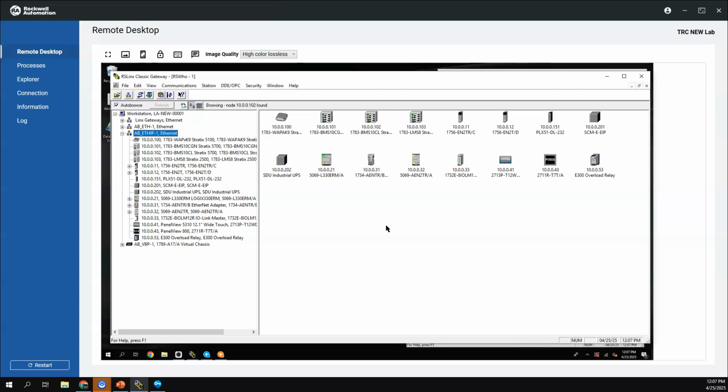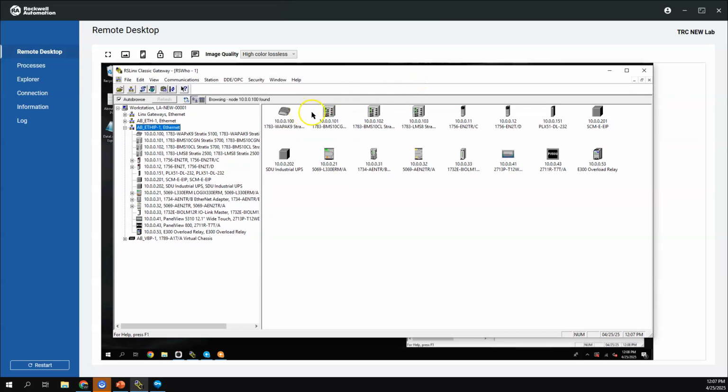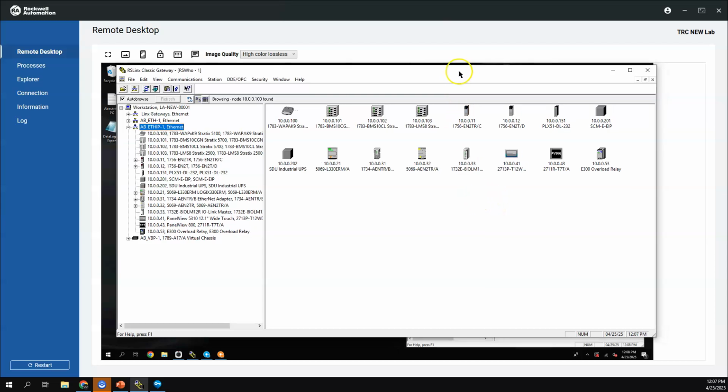One, I could use my computer. The software and programs are installed on my local computer here where I'm working currently. I can open up RSLinx and I can see everything. So if I wanted to, I could open up Studio 5000. I can open up CCW. I can open up any of the software tools on my local computer and make a VPN connection to those devices there remotely. So if I wanted to troubleshoot the ControlLogix program, open up Studio 5000, open the project, connect to that controller, and view what's going on with it, and make changes if I had to.